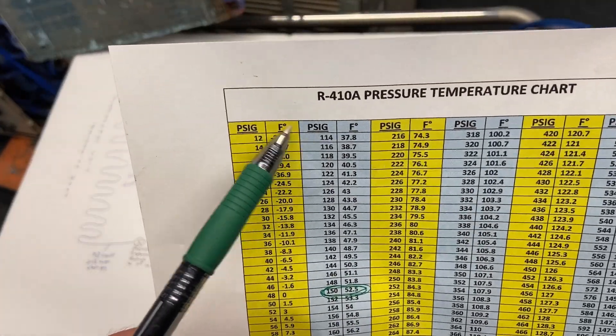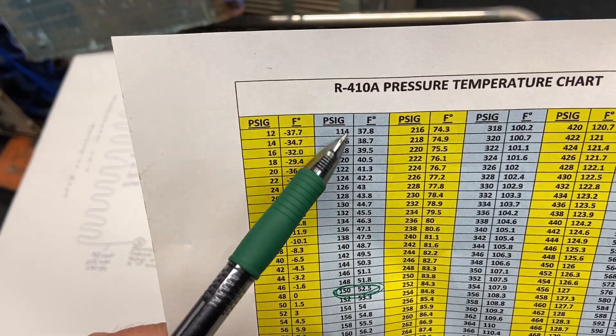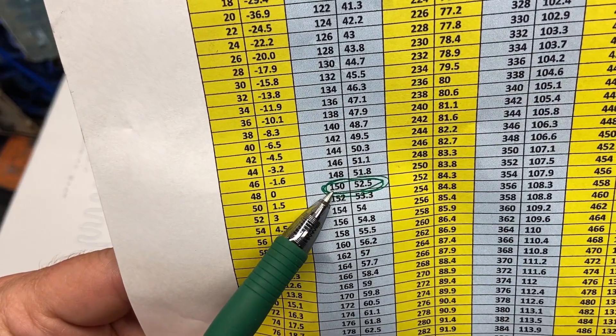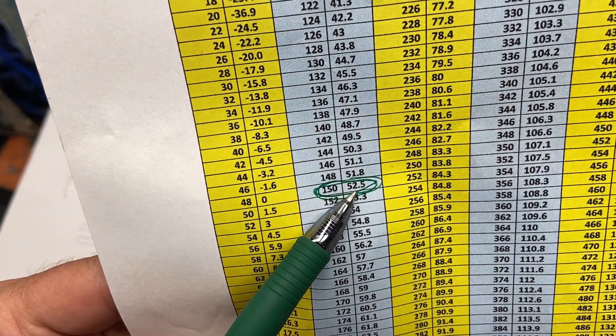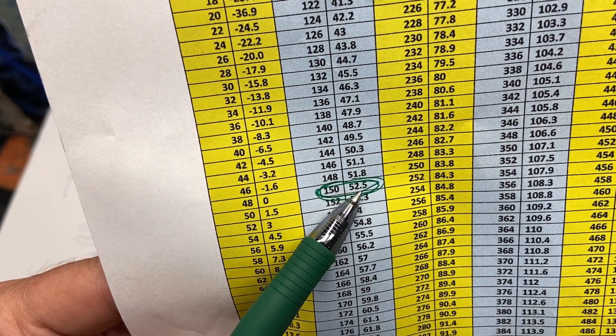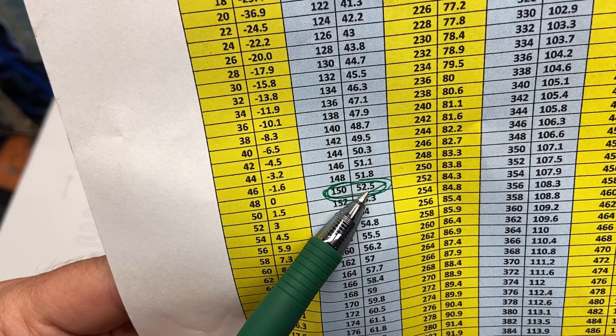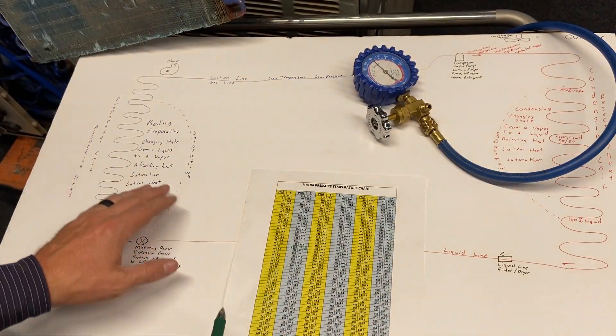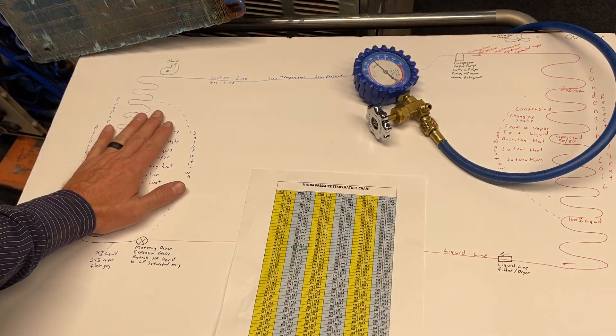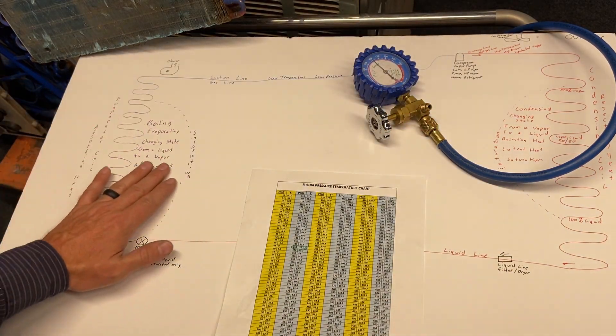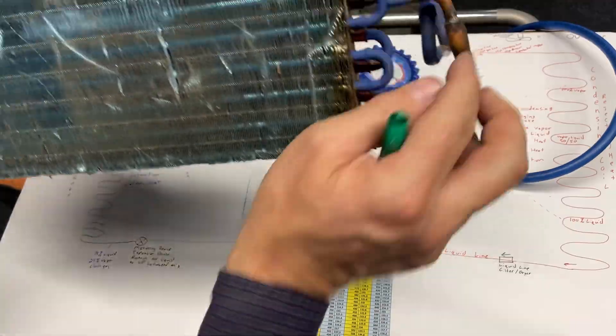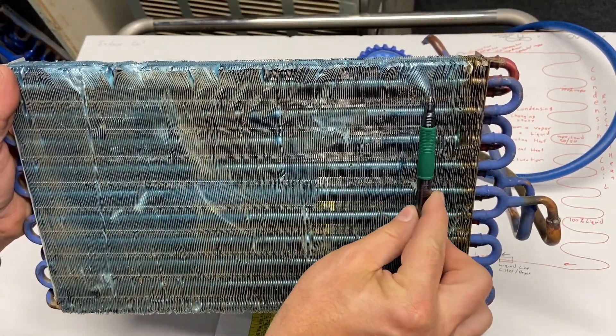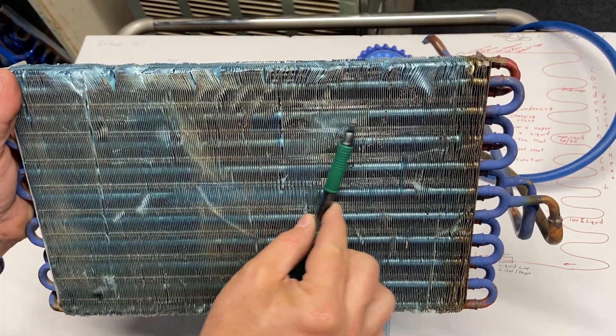Here's our temperature-pressure chart — pressure and temperature. If I scroll down and find 150 PSIG, that converts to a saturated temperature of 52.5°F, also called a boiling temperature of 52.5 or an evaporator temperature of 52.5. The pressure is the same throughout the whole low side, but that 52.5°F is taking place right through the majority of the evaporator coil.